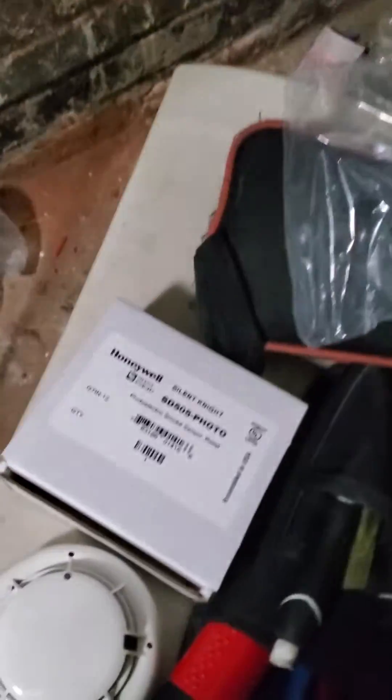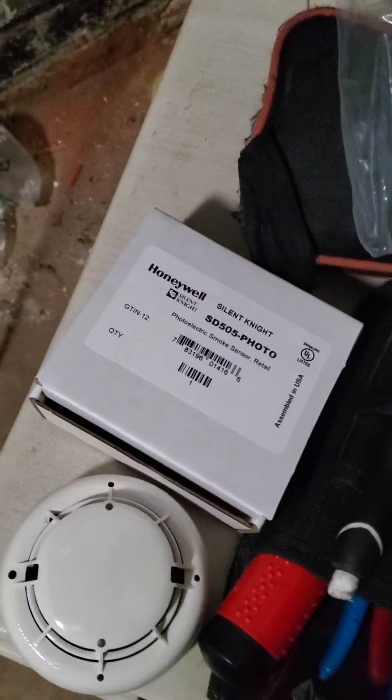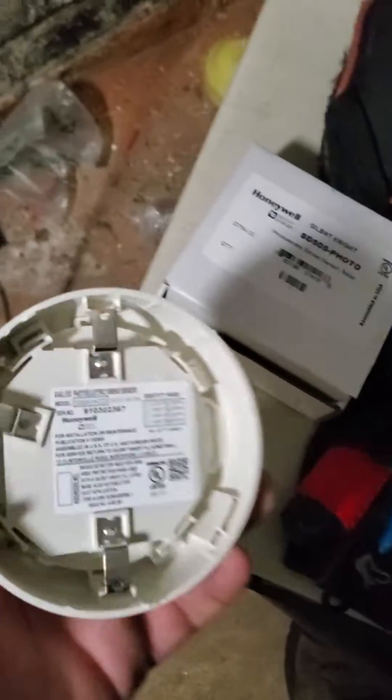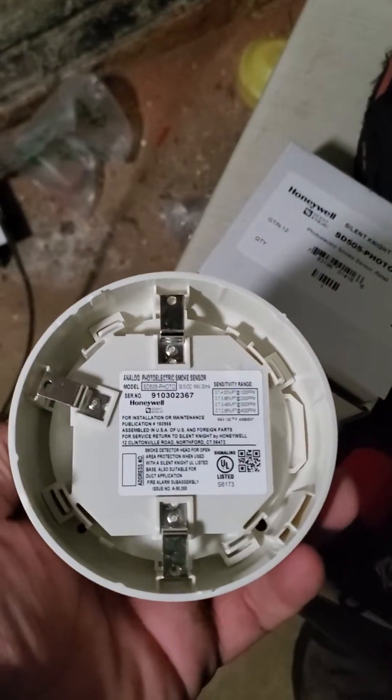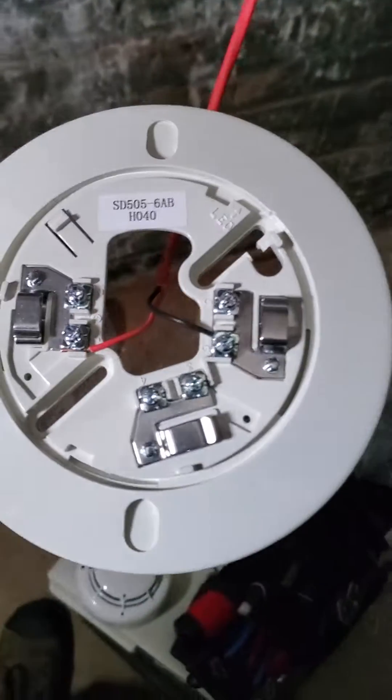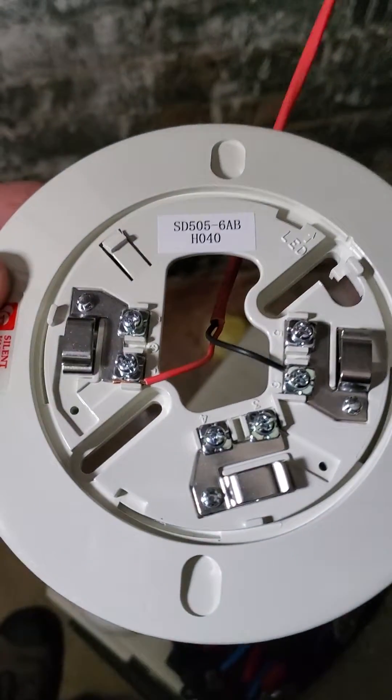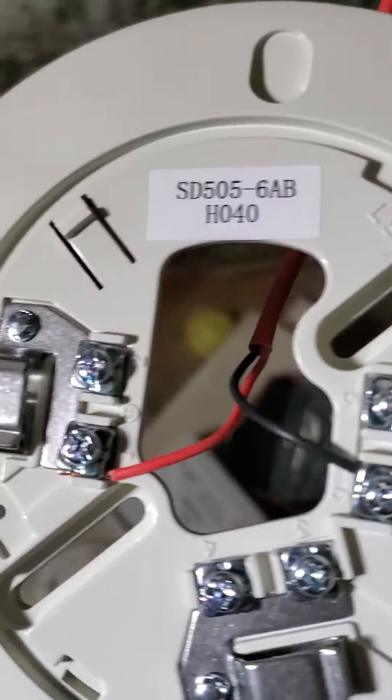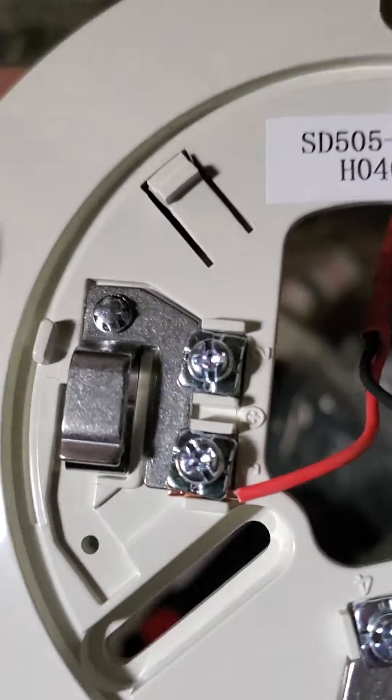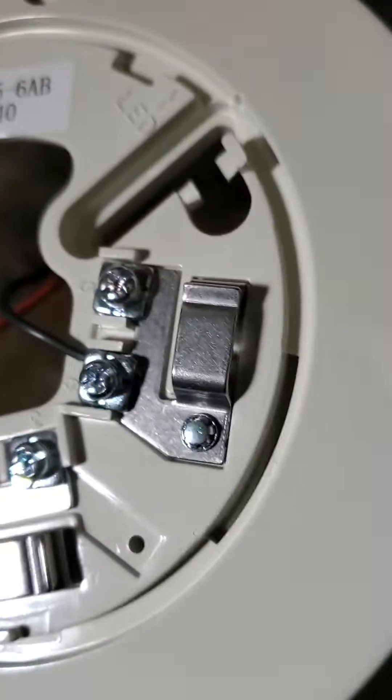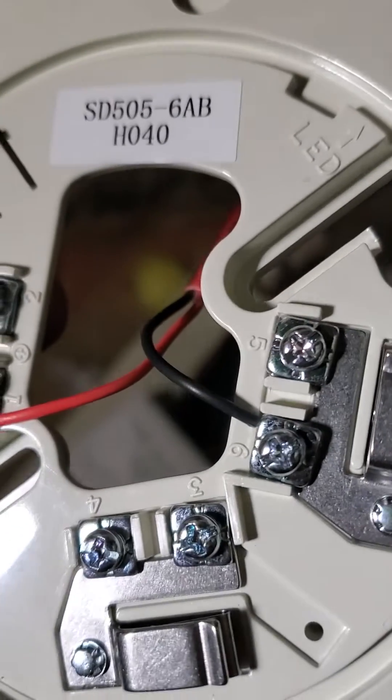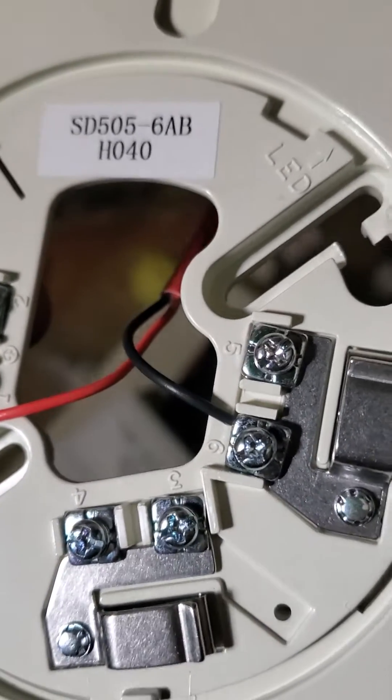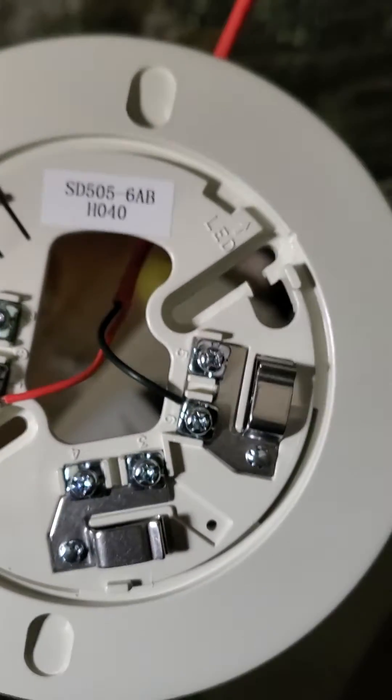Alright, we're going to be programming an SD505 photo. These do not have the dip switch addresses. You have to mount a wire to the base. The positive will go to positive terminal one, the negative will go to six or five. Then you plug in your smoke.